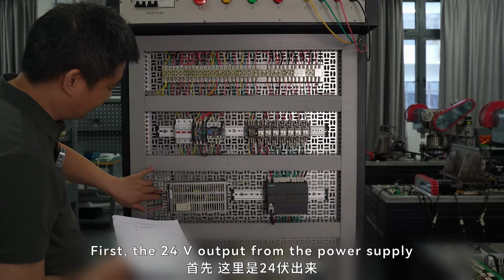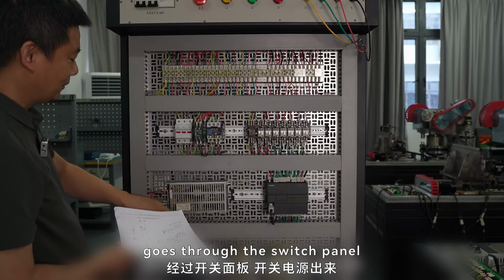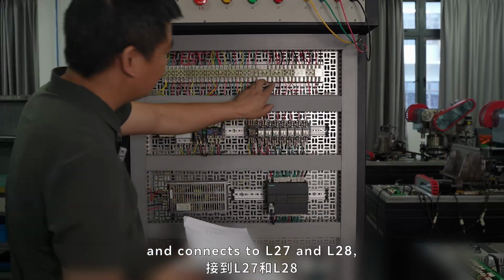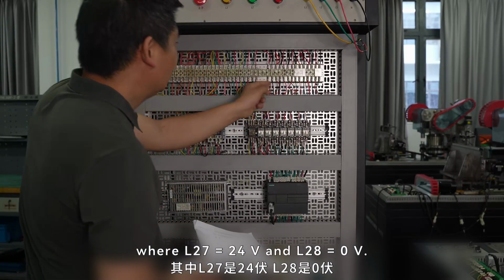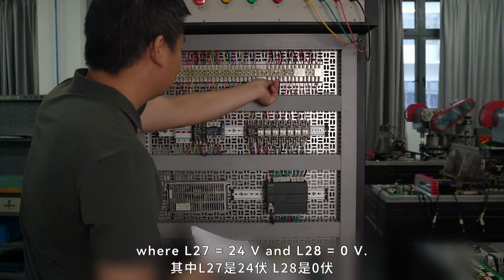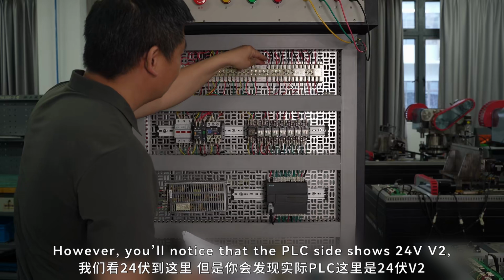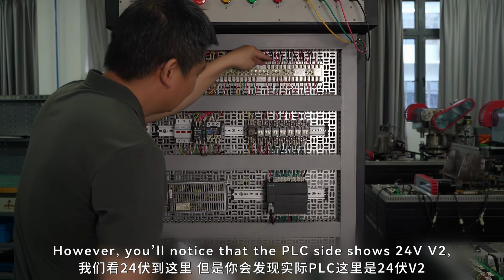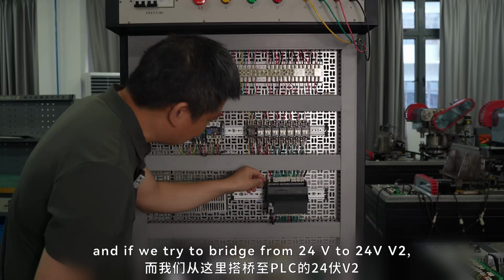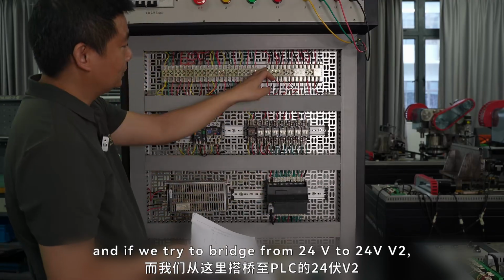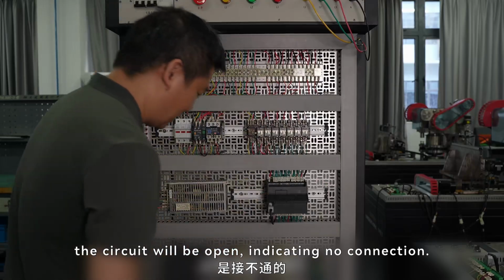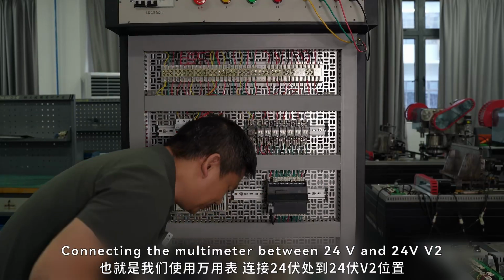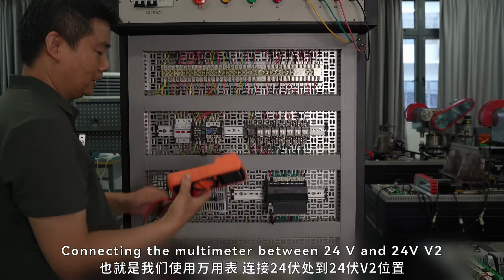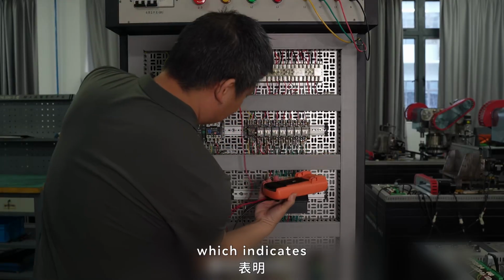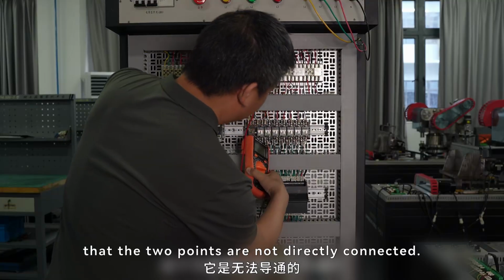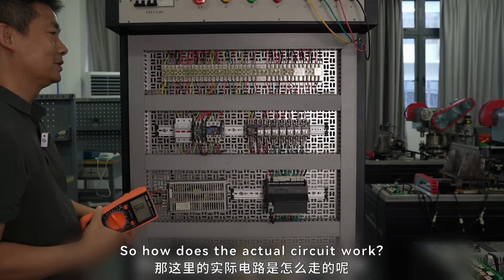First, the 24 volts output from the power supply goes through the switch panel and connects to L27 and L28, where L27 equals 24 volts and L28 equals 0 volts. However, you'll notice that the PLC side shows 24 volts V2. And if we try to bridge from 24 volts to 24 volts V2, the circuit will be open, indicating no connection. Connecting the multimeter between 24 volts and 24 volts V2 produces no beep, which indicates that the 2 points are not directly connected. So how does the actual circuit work?